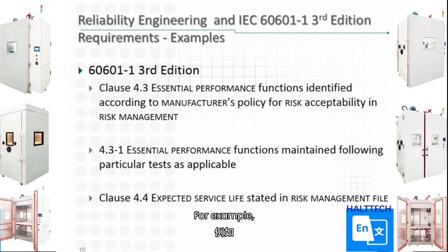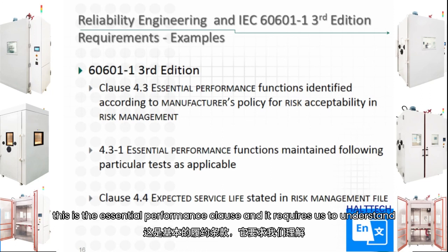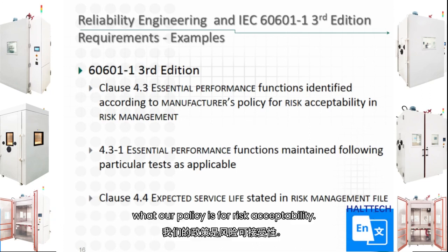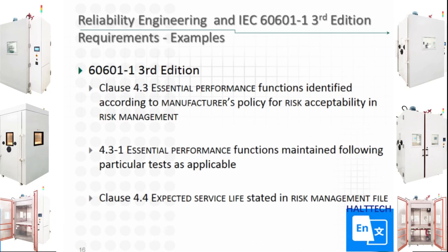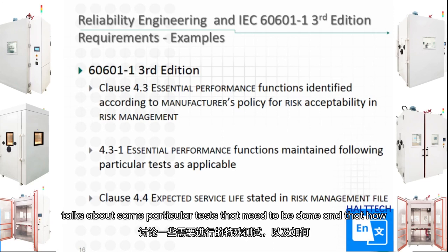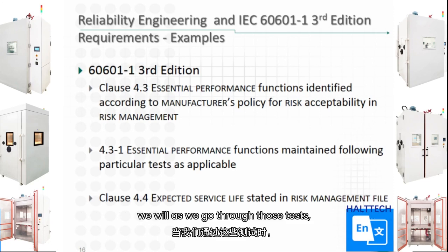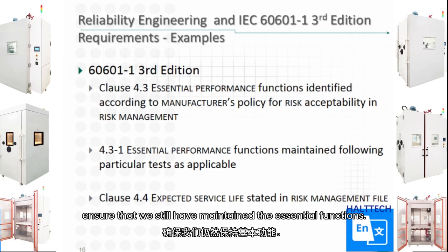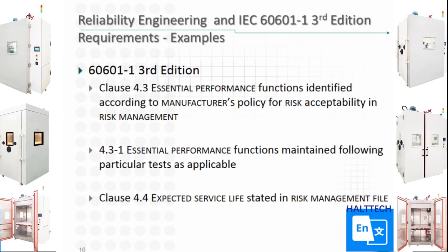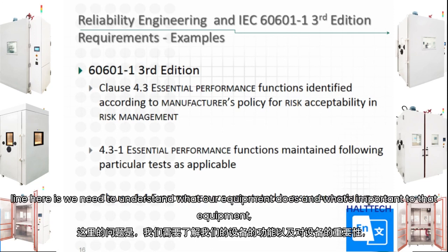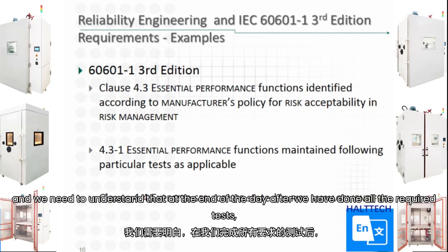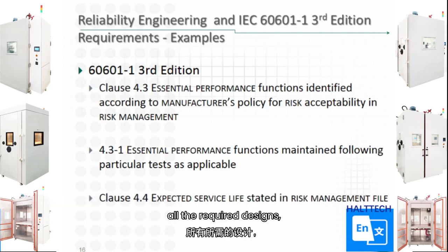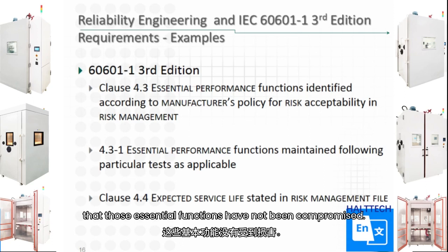In clause 4.3, for example, this is the essential performance clause, and it requires us to understand what our policy is for risk acceptability. Clause 4.3-1 talks about some particular tests that need to be done, and how, as we go through those tests, we ensure that we still have maintained the essential functions. So bottom line here is we need to understand what our equipment does and what's important to that equipment. And we need to understand that at the end of the day, after we have done all the required tests, all the required designs, those essential functions have not been compromised.